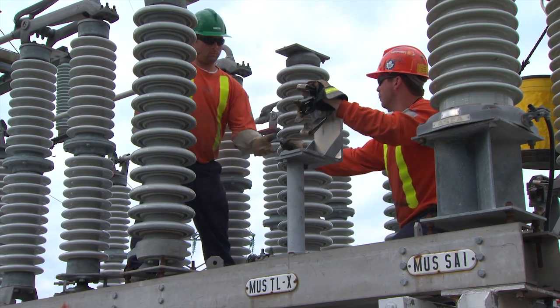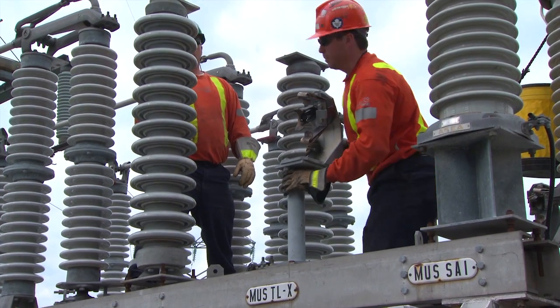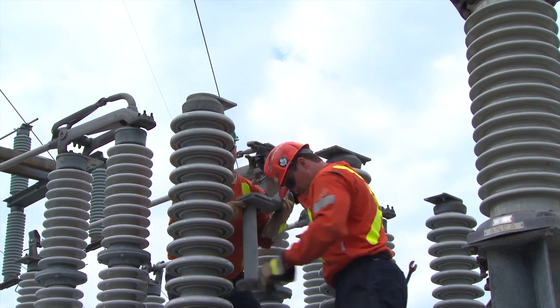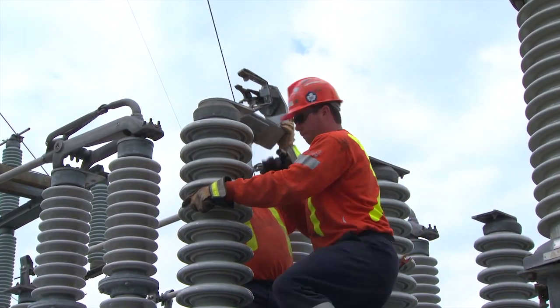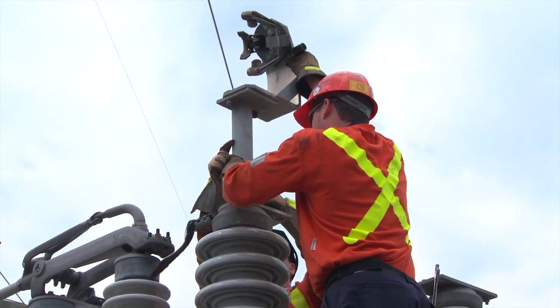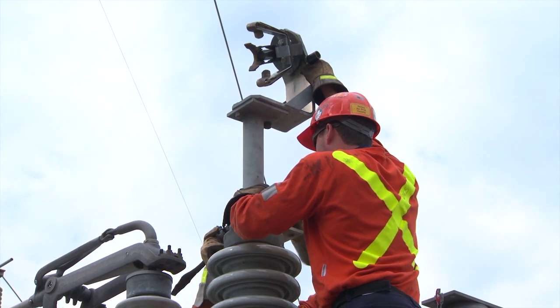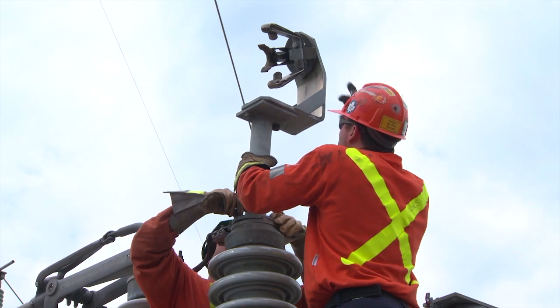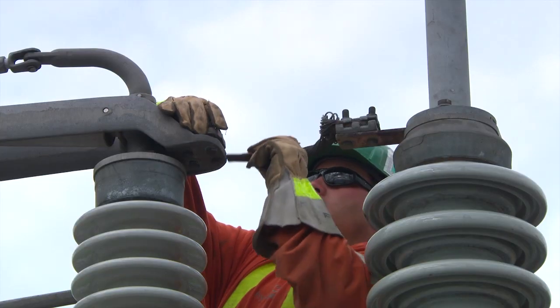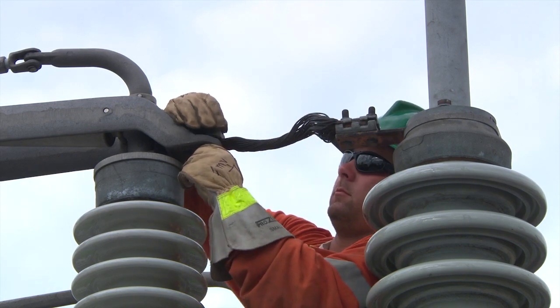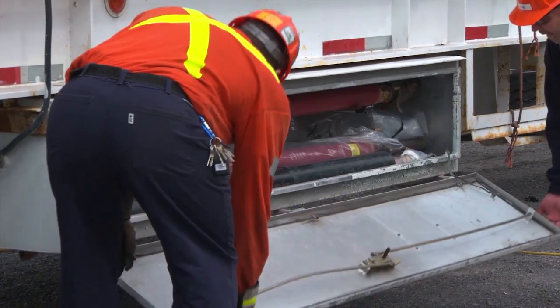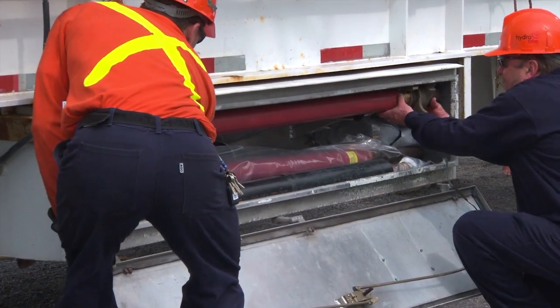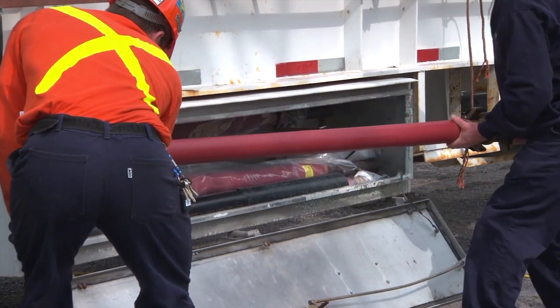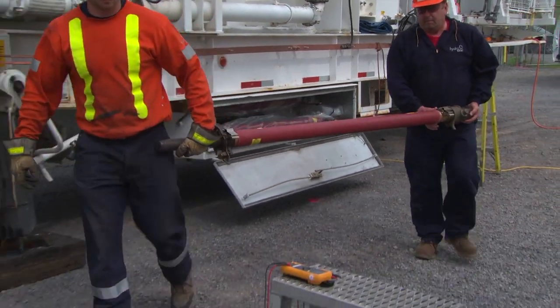Remove the high-voltage fuse jaws from the shipping position and install them on the adjacent high-voltage insulator. Remember to install the jumper between the base of the high-voltage fuse and the high-voltage switch on all 3 phases. Remove the high-voltage fuses from the storage cabinet and place them on a work surface for inspection.